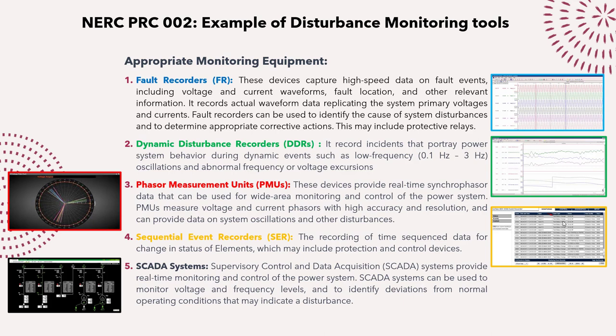Fault recorders are devices that capture high-speed data on fault events. They record voltage and current waveforms, perform fault location detection, and capture element information such as fault type, voltage dip, current dip, harmonics, sequence components, which relay operated, and what type of fault initiated — all as actual waveform data replicating primary system voltages and currents. Fault recorders can identify the cause of system disturbances and determine appropriate corrective action; they may be part of a protective relay or a standalone fault recorder for the entire substation.